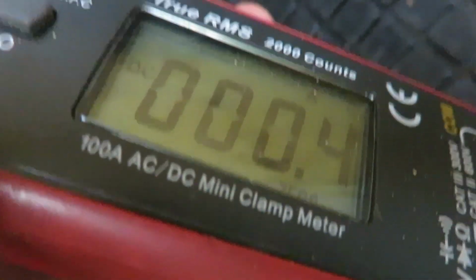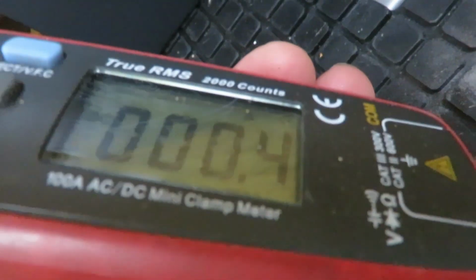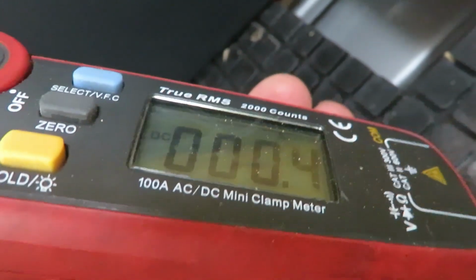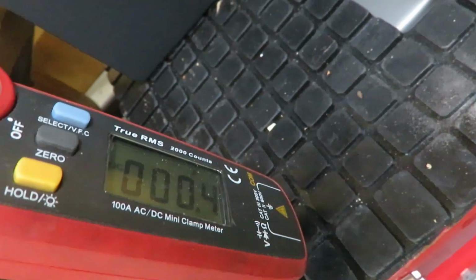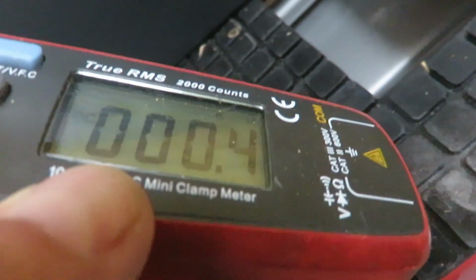Let's see if it zeroes out when I take it off. Yeah, so the current on there now is what the inverter is using for idle current. If I go to a different range - 400 millivolts, or milliamps I mean - so not quite half an amp. That's how much it takes just for running the inverter.